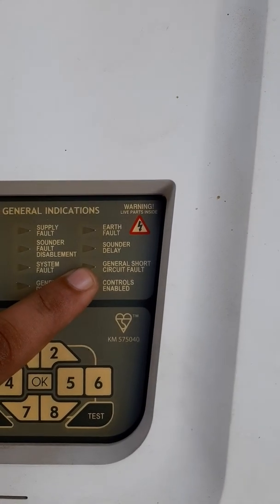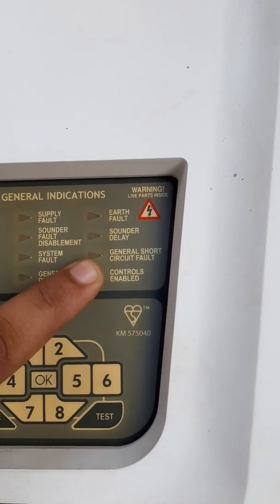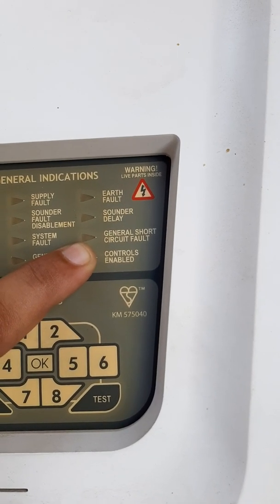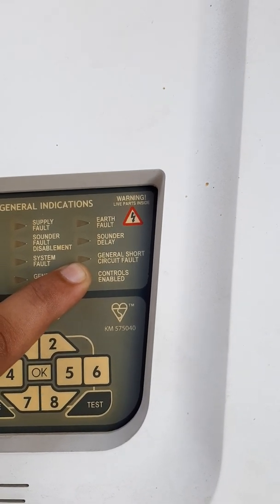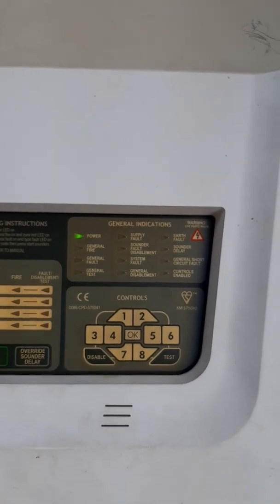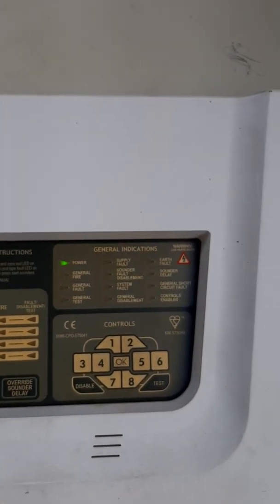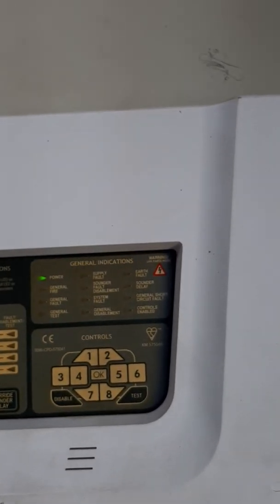The third fault is short circuit. If the short circuit indicator is blinking, you check the device zone wiring one by one and check every device connection.